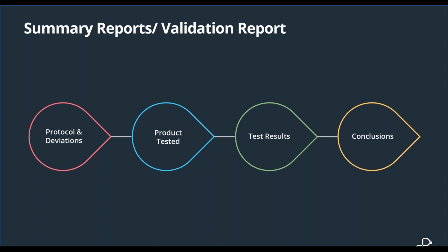If you're going into a summative study and you're not quite sure what you're going to find, the unexpected surprise notwithstanding, then really all you're doing is a very expensive formative study. So you really need to be in a position where you're fairly confident what those results are going to be.